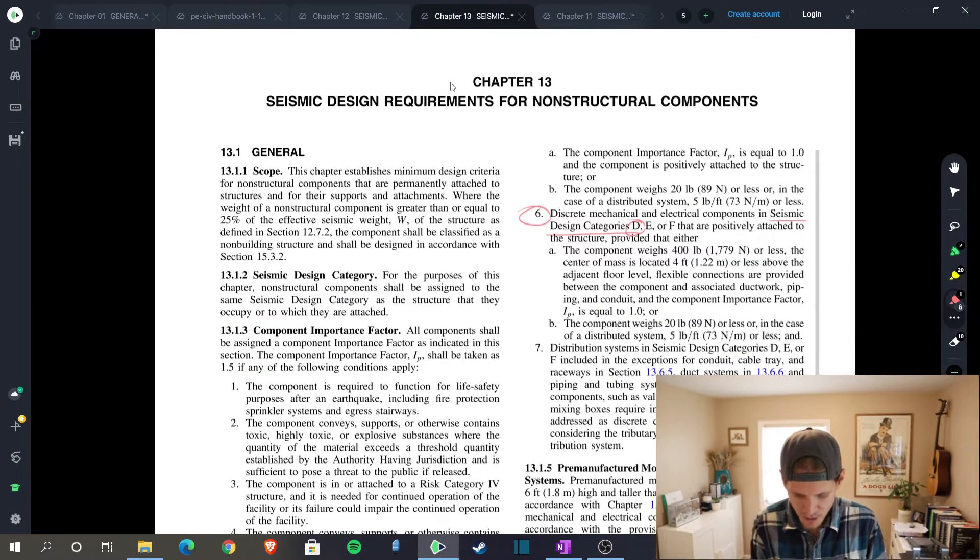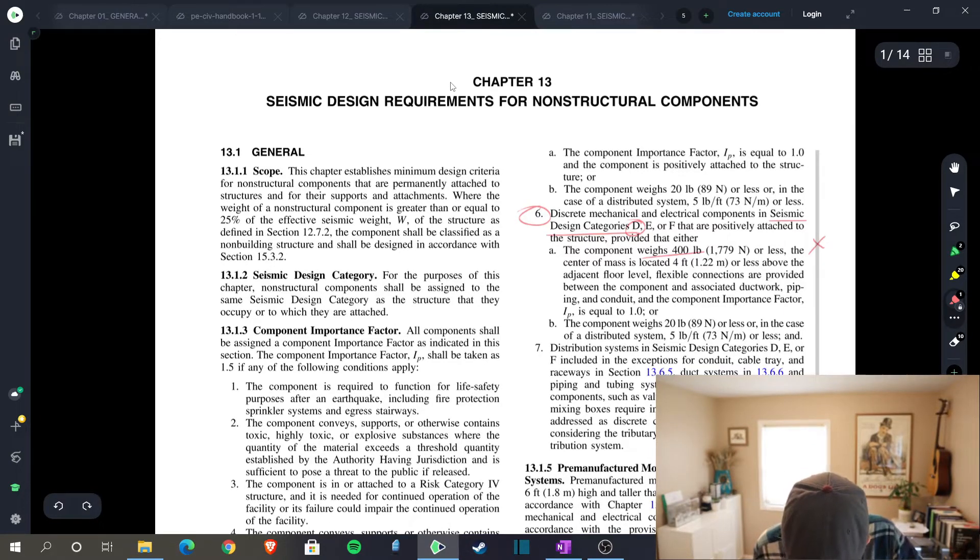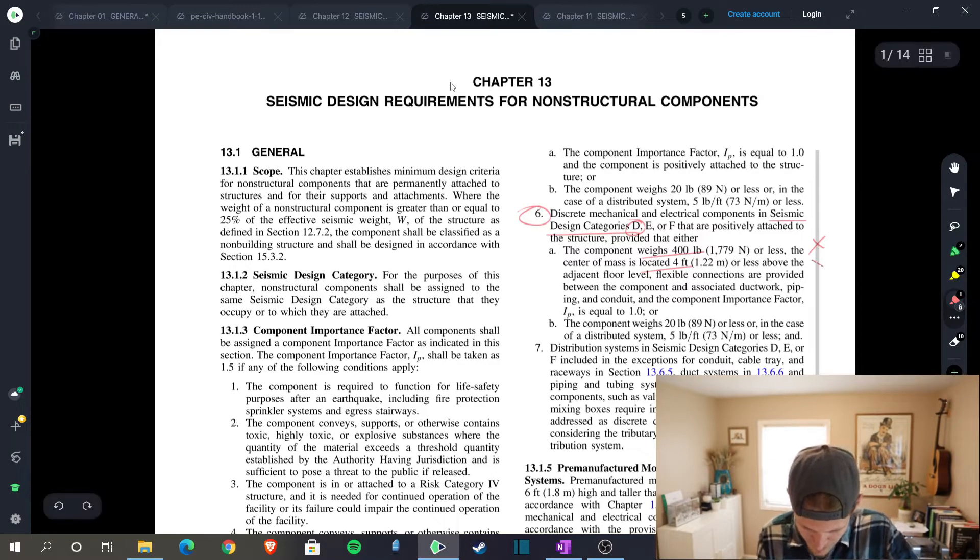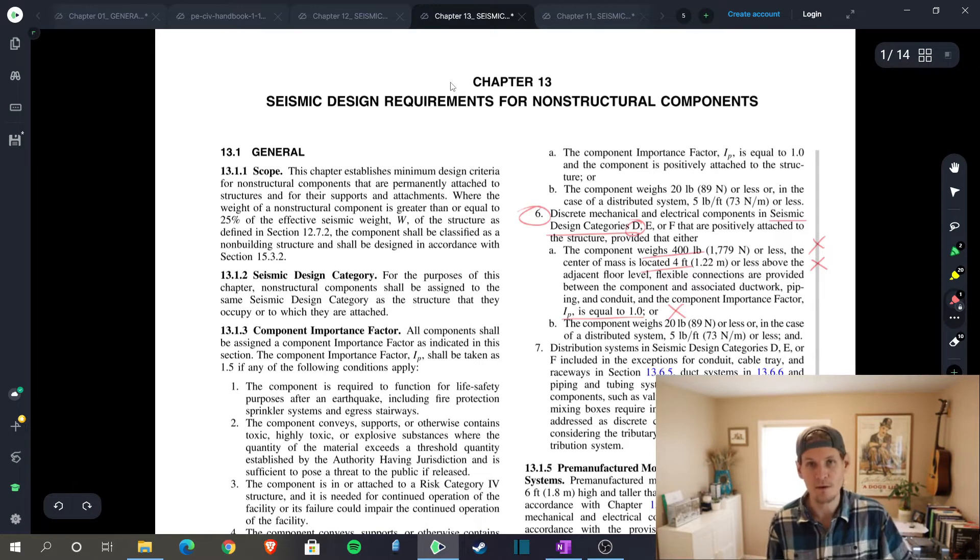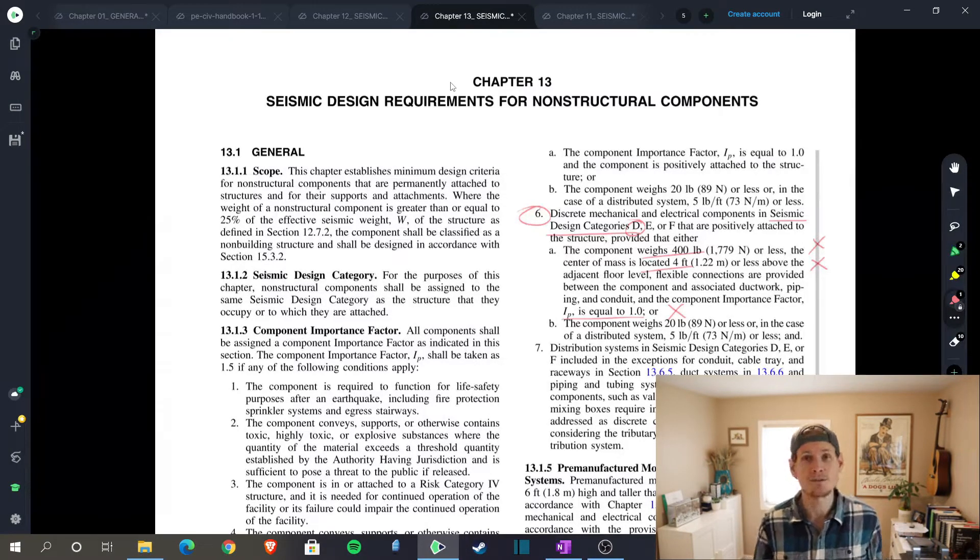What this passage is saying is that you are exempt if you're in seismic design category D and you're positively attached to the structure, so you do have some sort of anchorage provided, that either the component weighs 400 pounds or less—well, our unit is a thousand pounds, so we don't work out there. The center of mass is located four feet or less above the adjacent floor level—we're five feet, so that doesn't work out. And lastly, the importance factor is equal to 1.0—we also don't work out, we have 1.5. So strike three, we need to design this anchorage, but that's okay, that's why we're here today, right.